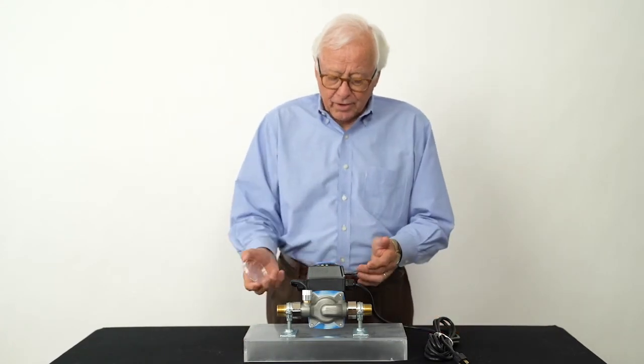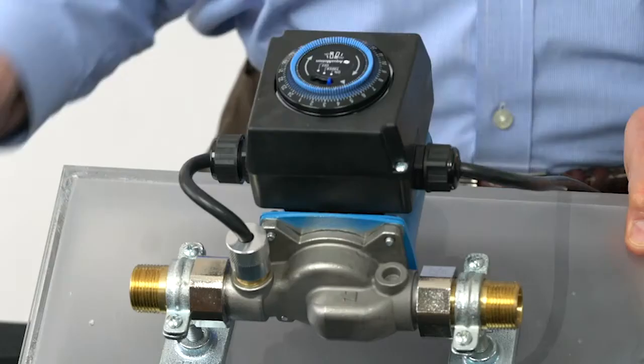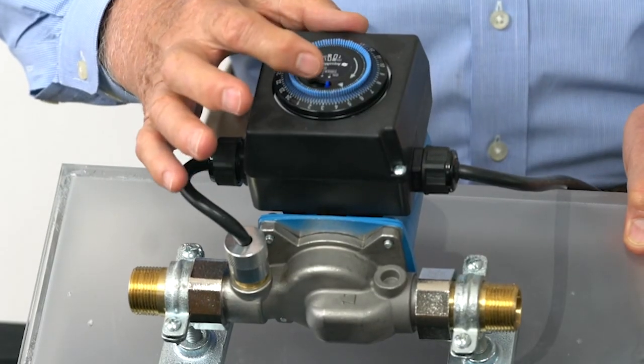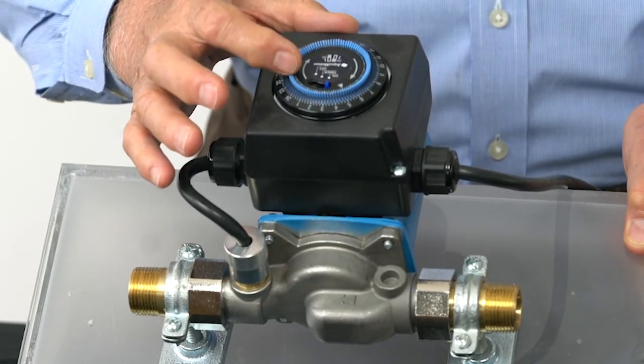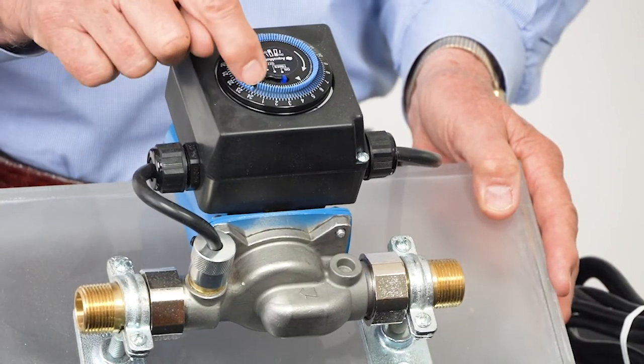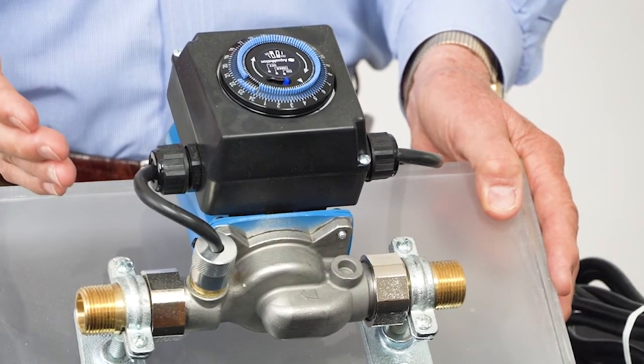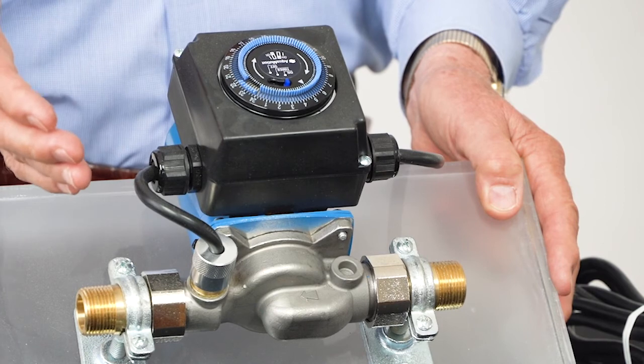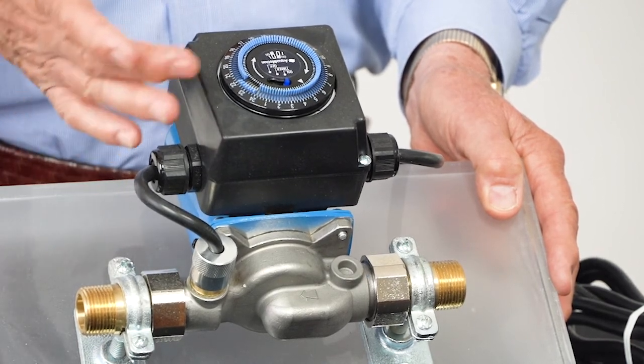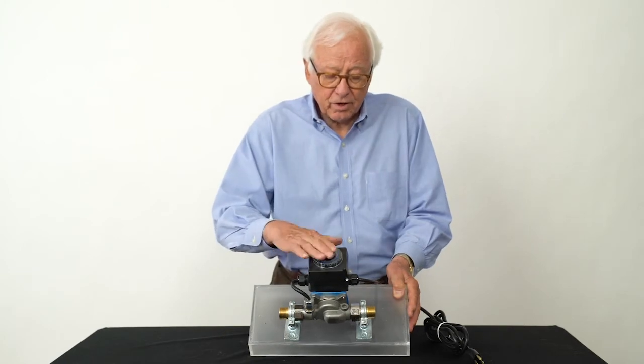This is a kit for dedicated return lines. The pump is installed on the return line before the tank or tankless heater, and it provides a special long tailpiece so you can mount it against the wall for a rigid application. A sensor senses the temperature — when it reaches 85 degrees in the return line, the pump turns on for a minute to a minute and a half, moving water in the dedicated return line into the cold line and out through the hot supply line. The timer has three positions — on, on-timer, and off — and each 15-minute tab pushed out activates the system.